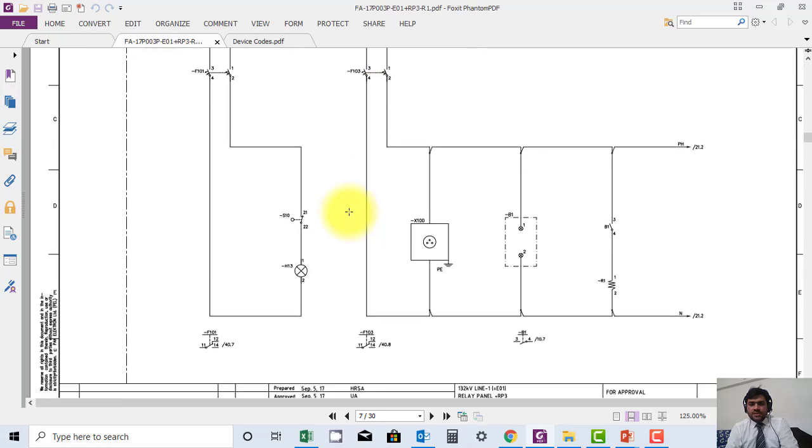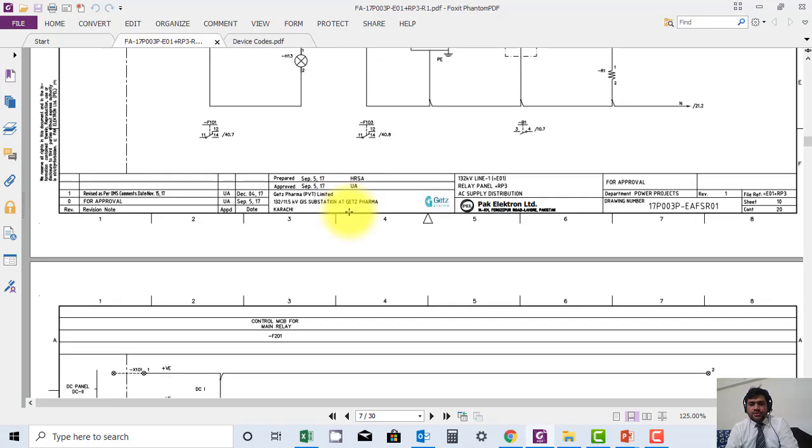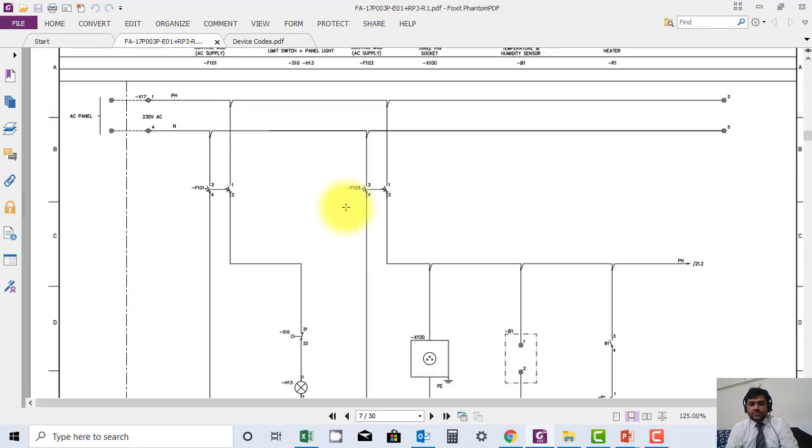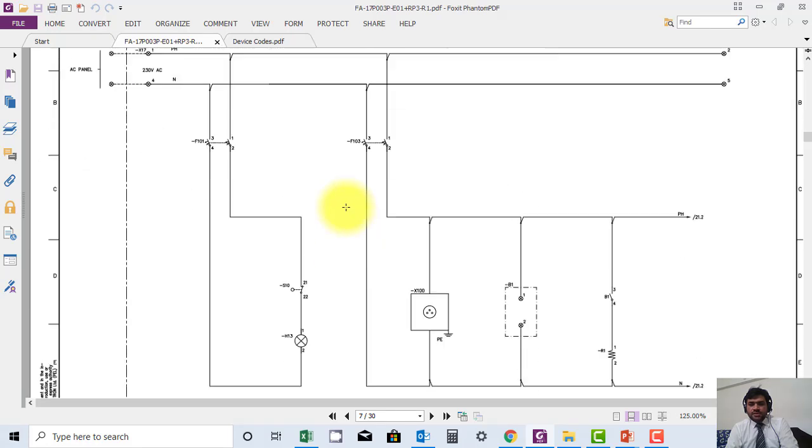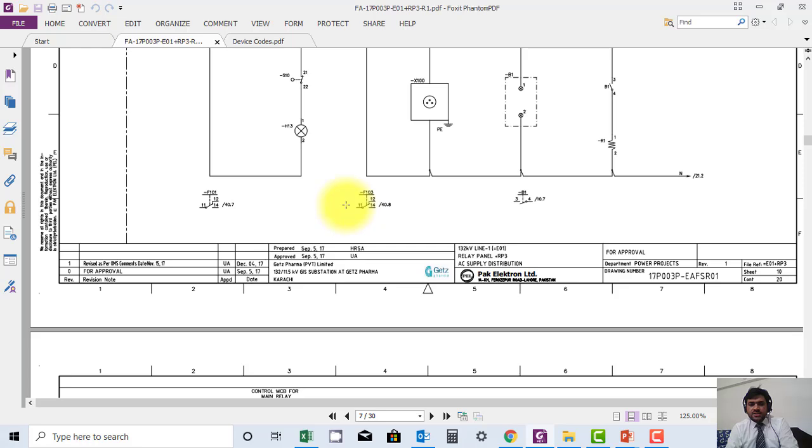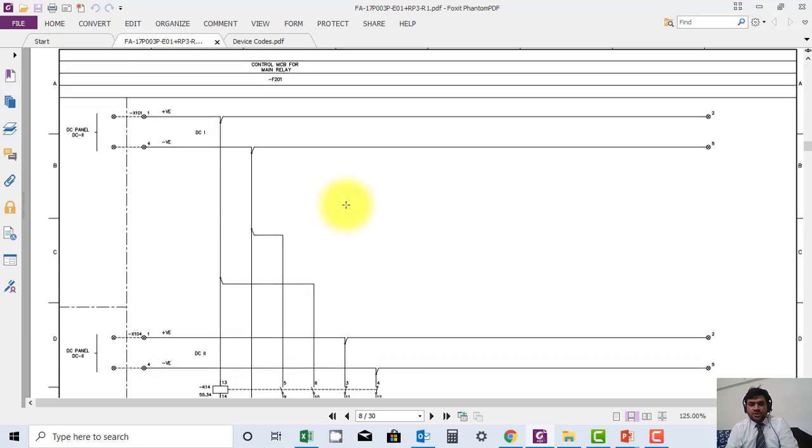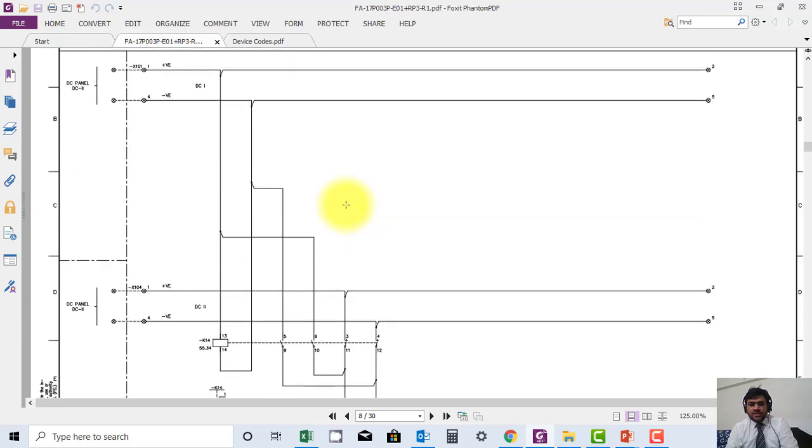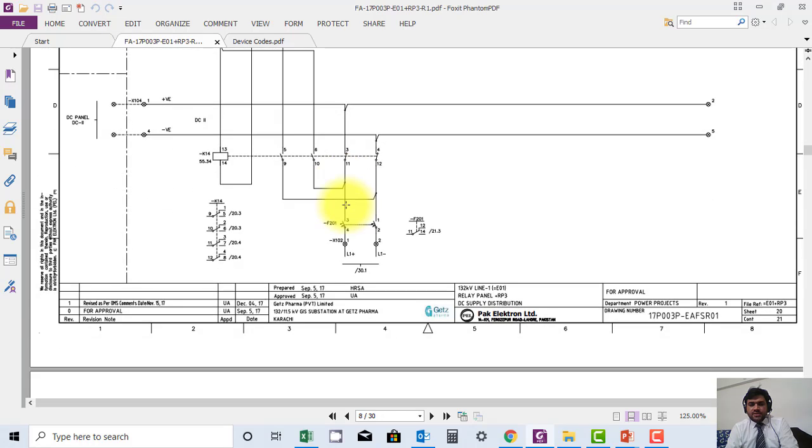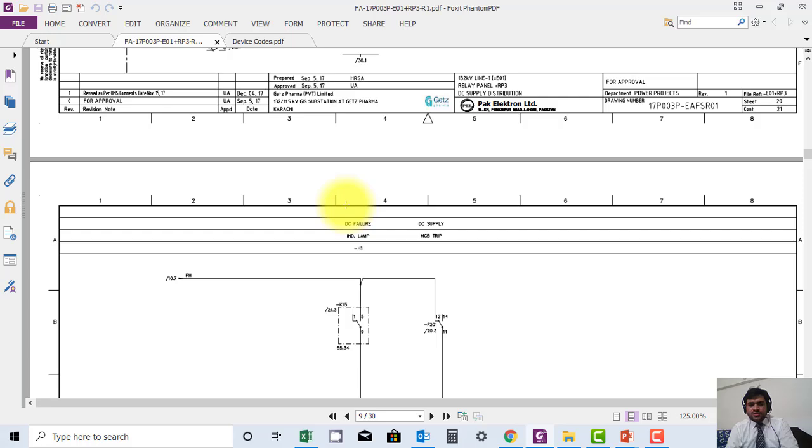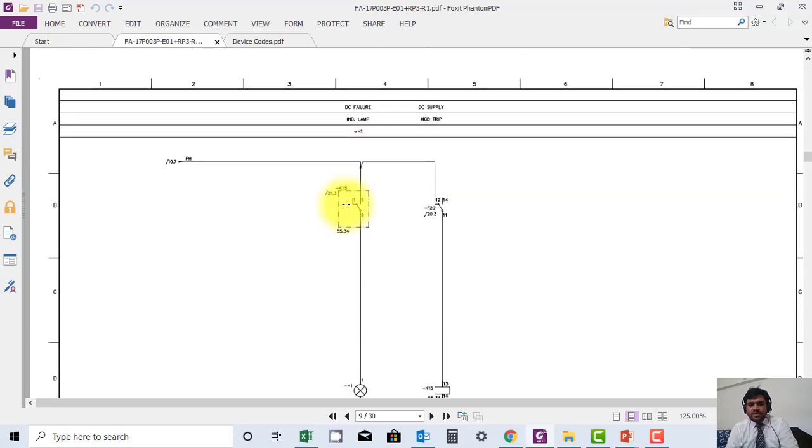Check if there is any mixing between AC and DC loops. Another thing: inside the panel, the DC wiring and AC wiring should be separated and should have separate entrance.